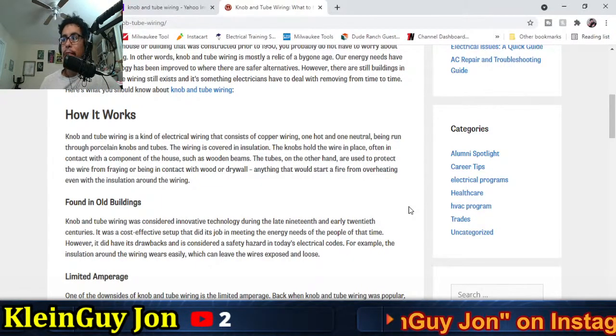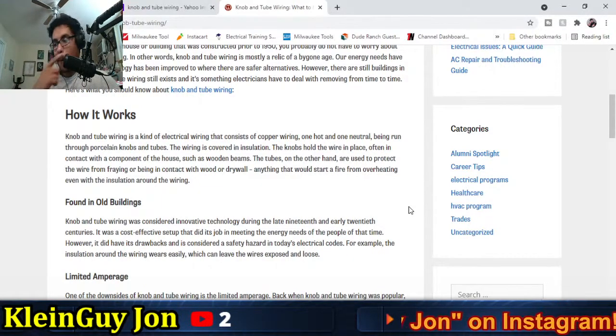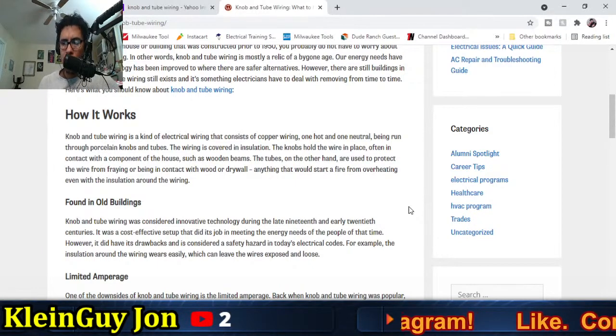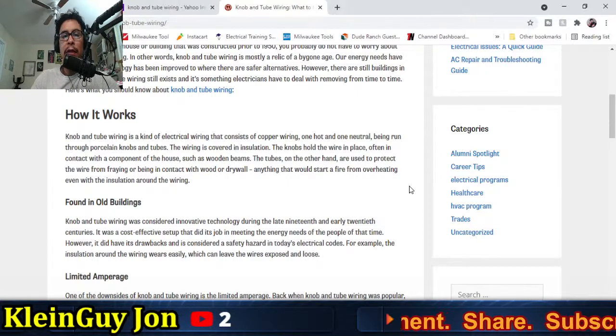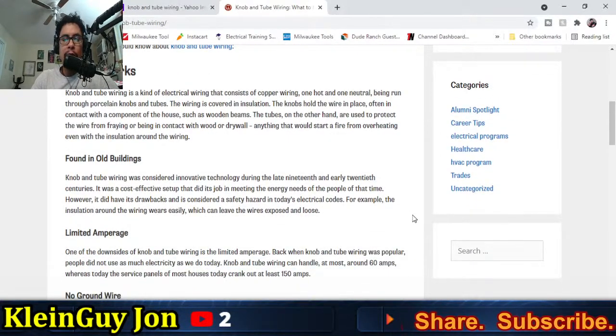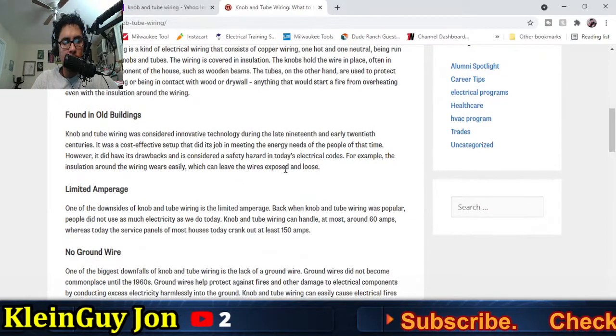Typically these wires were number 14 wire, and I believe coming from the meter would be number 10 wire, if I'm not mistaken, to feed your main disconnect and the main fuse, and then everything else would just be 14 gauge wire.